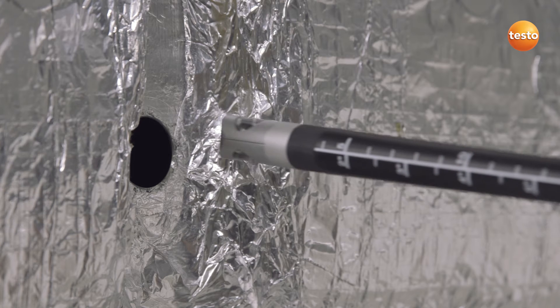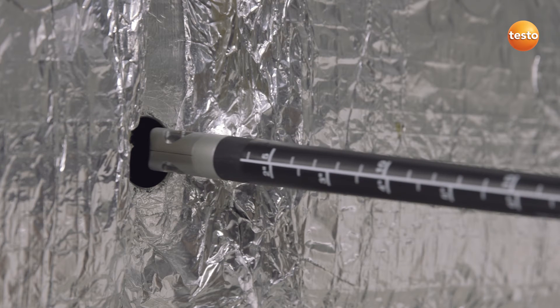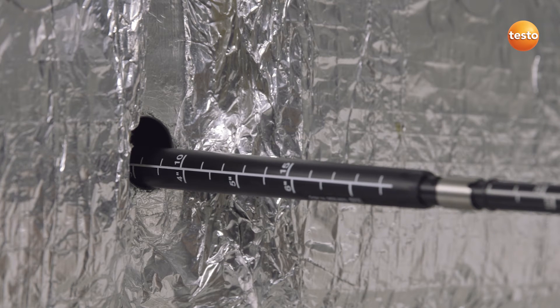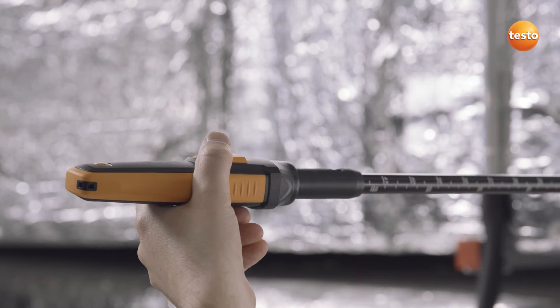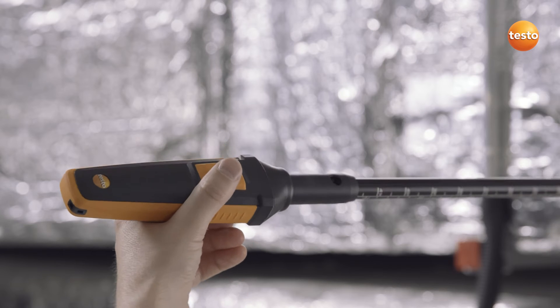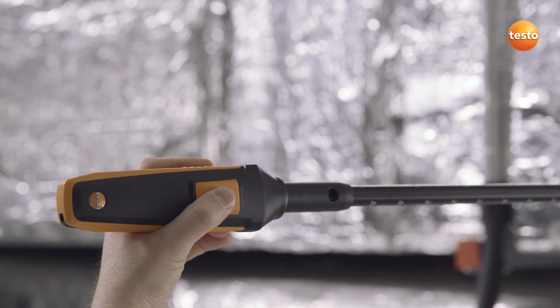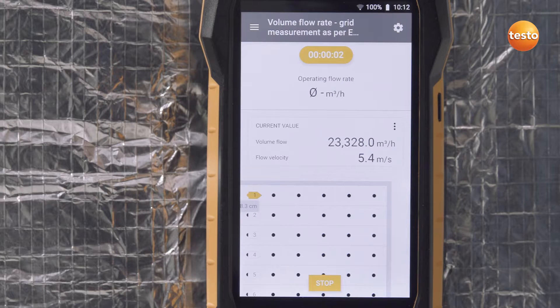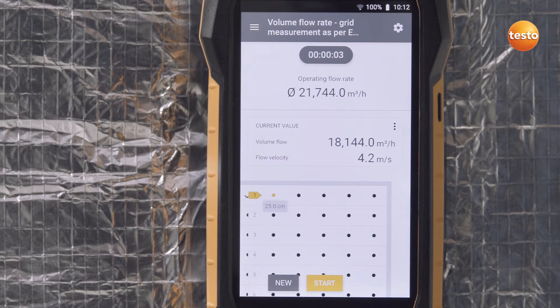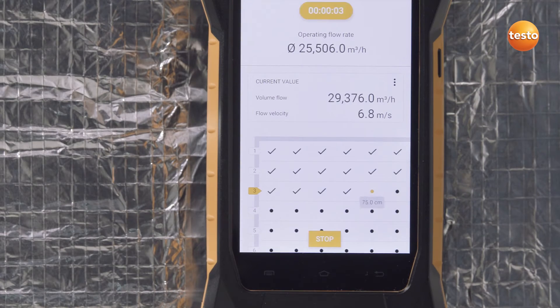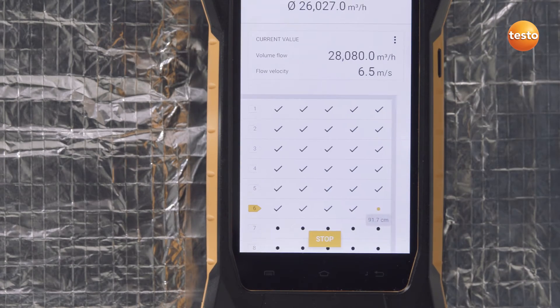Now, insert the anemometer to the corresponding depth into the aperture. This is done quickly using the easily legible scale on the telescope and anemometer. The measurement begins as soon as you press the button on the handle. After 3 seconds — the selected measurement interval — a mean value is calculated and the new insertion depth is displayed.